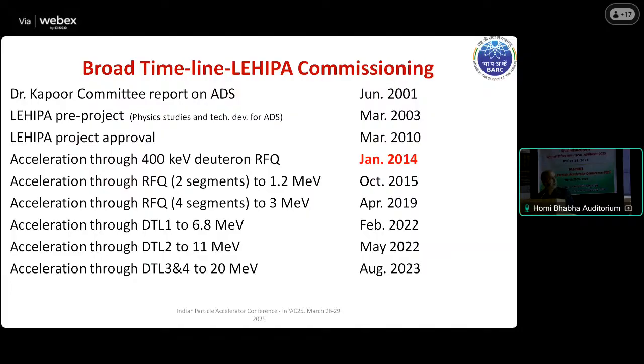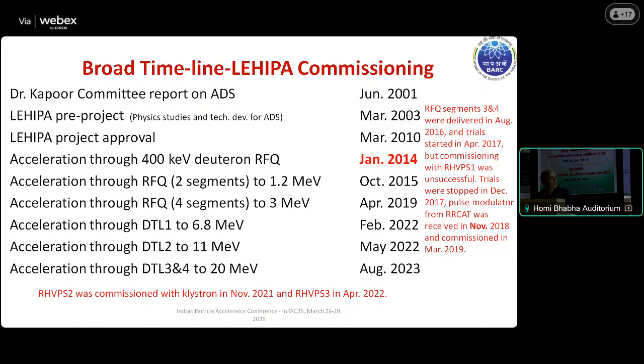After that it was a fairly quick process up to 11 MeV. After 11 MeV we integrated tanks 3 and 4 in one shot, and finally we accelerated the beam to 20 MeV. There were delays related to the regulated high voltage power supply, which was a very technically challenging job, done in collaboration with IPR and ECIL and different divisions of BARC, including CNID. In between, RRCAT gave us the pulse modulator, which was very stable, and we accelerated the 3 MeV beam with that, and still we are running with that stable pulse modulator, which will be replaced with the regulated high voltage power supply in future. So the power supplies number 2 and 3, which are 100 kilovolt, 20 ampere, are working very fine within the required stability of 1%.